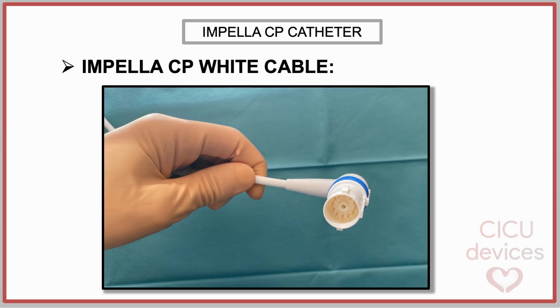The Impella CP white cable terminates in a circular multi-pin connector, designed for precise electrical and optical interfacing with the console. The connector features 12 gold-plated contact pins, arranged concentrically around a central port, which houses the optical fiber used for real-time pressure sensing in the Smart Assist version. The contact pins are slightly elevated above the plastic surface, forming male terminals that mate directly with the corresponding female contacts inside the console port.